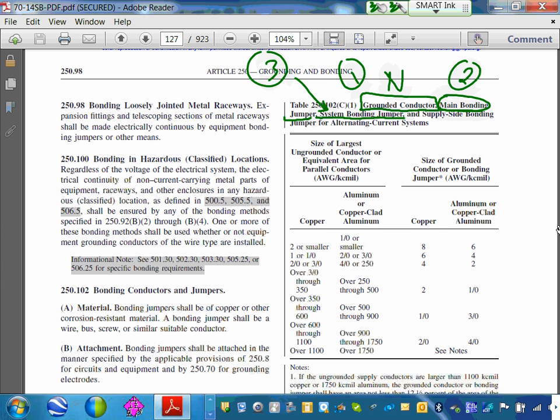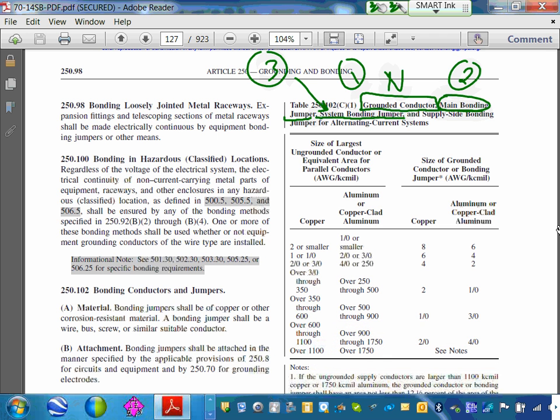Supply side bonding jumper. I want to spare you a little bit. This is basically a fancy name for when you bring the service conductor, guys. Now this is non-metallic, so you don't do that. If that was metallic, when you bring the service conductor, they bond the conduit. They put a clamp on the conduit and they bond the conduit. The fancy name for it is supply side bonding jumper.